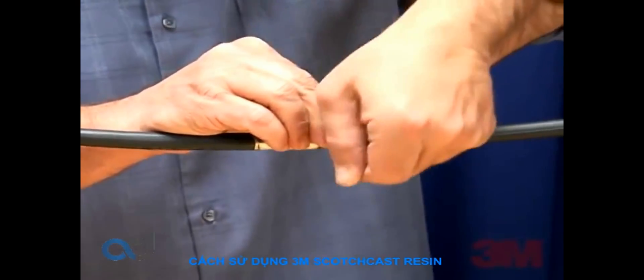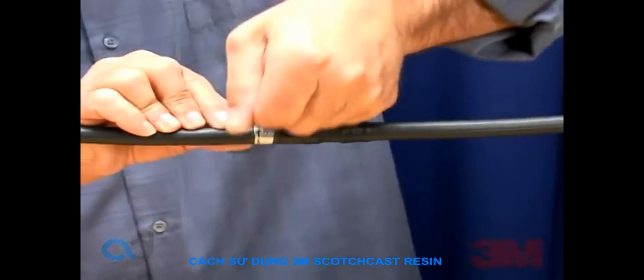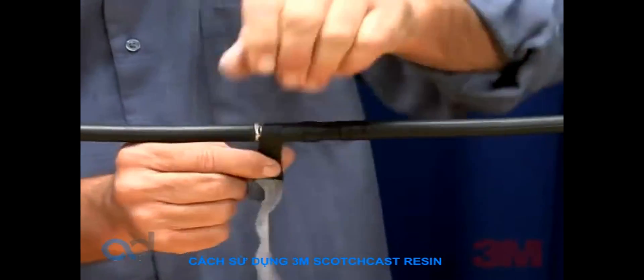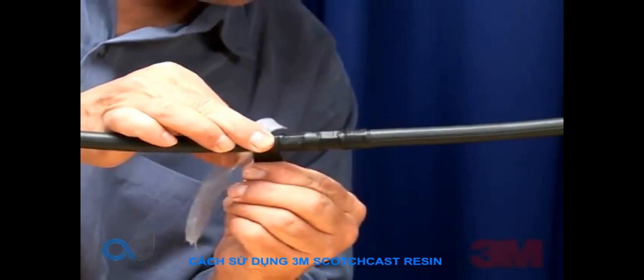Apply one layer of half lap Scotch brand electrical tape 23 over the connector area only. Do not wrap tape onto the pencil area. Note that connectors are not included with the kit and should be ordered separately. Each kit makes one splice.